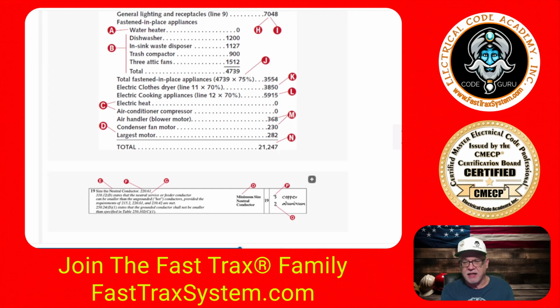We have to find the largest motor, but it's only the largest motor that has a neutral contribution, not just the largest motor, because obviously there may be an air conditioner compressor that is the largest motor, right? But remember, that doesn't have a neutral load. So we're going to be looking for the largest motor that has what? That has the neutral contribution, okay? Makes sense? Okay, so in our case, it would be the in-sink waste disposer.